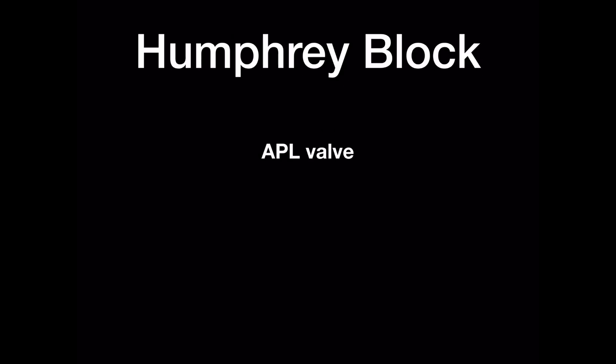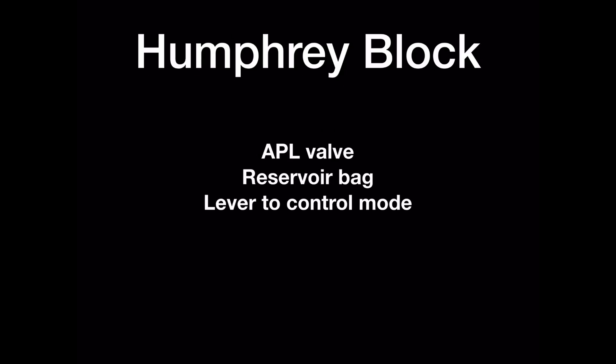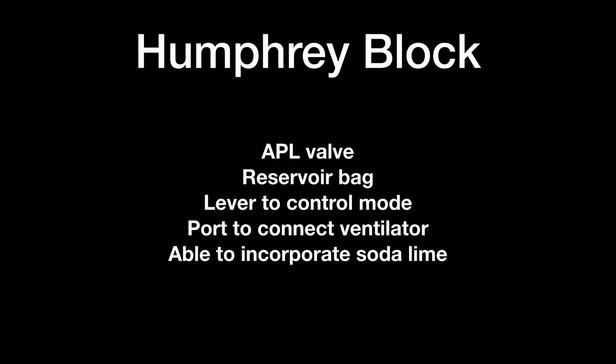The Humphrey block consists of an adjustable pressure limiting, or APL, valve, a reservoir bag, and a lever which is used to select either spontaneous ventilation mode or controlled ventilation mode — we will discuss this further in a moment. There is also a port to connect to a ventilator, and it is capable of incorporating a soda lime canister if required.